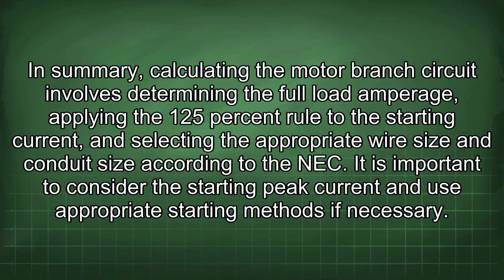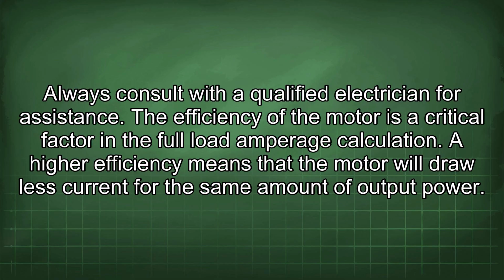In summary, calculating the motor branch circuit involves determining the full load amperage, applying the 125% rule to the starting current, and selecting the appropriate wire size and conduit size according to the NEC. It is important to consider the start and peak current and use appropriate starting methods if necessary. Always consult with a qualified electrician for assistance.